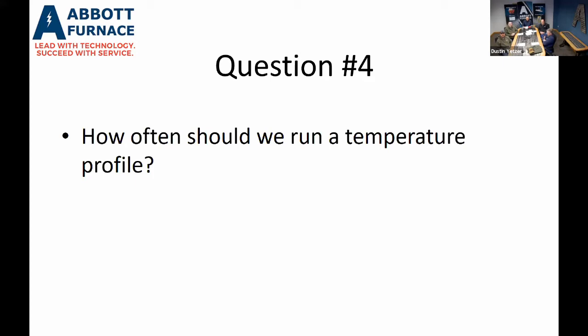Now, it's never a bad idea to do them more often, because what that begins to build is a historical record of changes in the equipment. Back to what Don mentioned about thermocouple degradation, you can see that in the temperature profile. If you have a company coming in to do your quarterly calibrations and they're not changing thermocouples, you can see that change in the temperature profile over time if you do it quarterly or biannually. So it can certainly help to identify a problem before it starts.